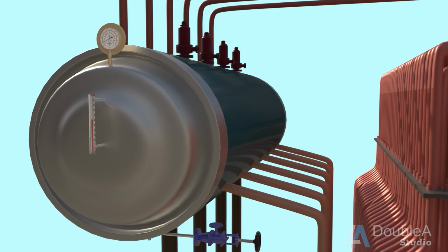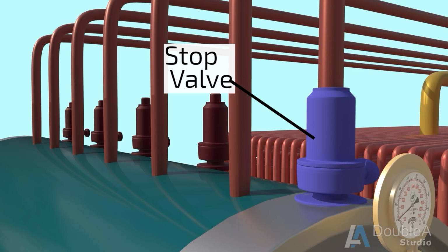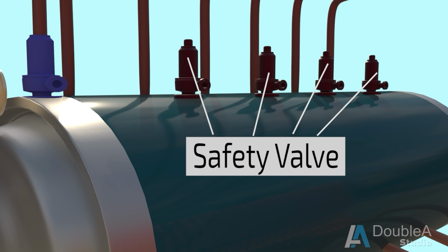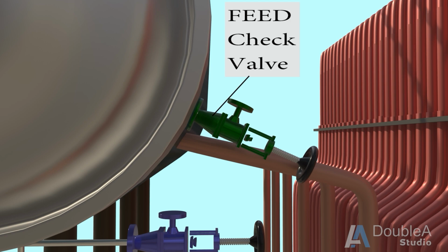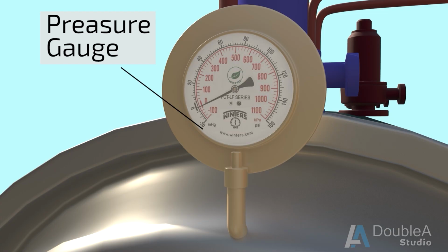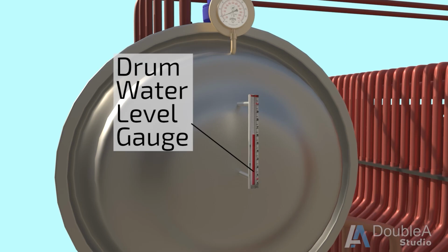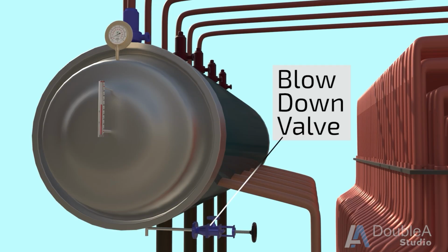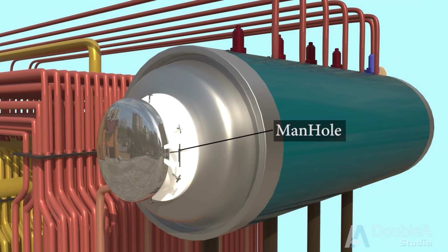We can see various mountings on the boiler drum like the main stop valve to stop or allow flow of steam from the boiler to the turbine. Safety valve blows off excess steam and maintains pressure inside the boiler drum. Feed check valve, which is NRV type, controls supply of feed water. Pressure gauge indicates pressure of steam. Drum water level gauge shows water level in the drum. Blow down valve controls dissolved solids in boiler water. Also, there is a manhole on the boiler drum body which allows entry for maintenance and cleaning during shutdown.